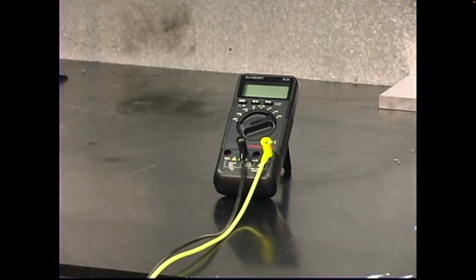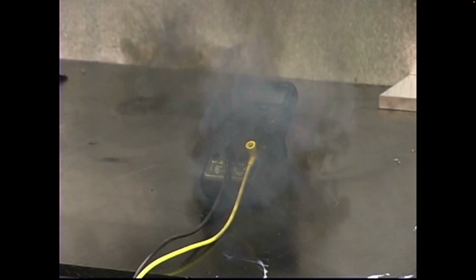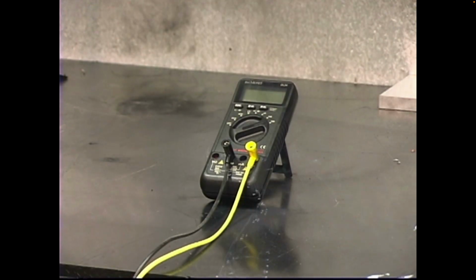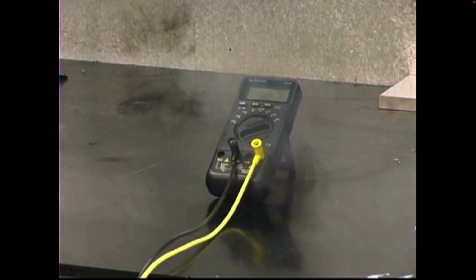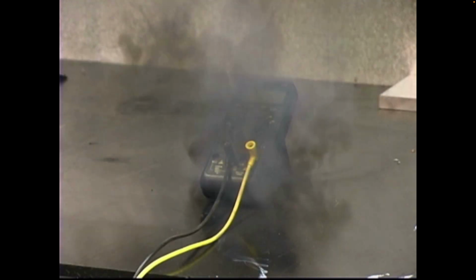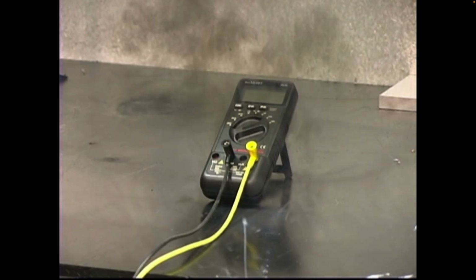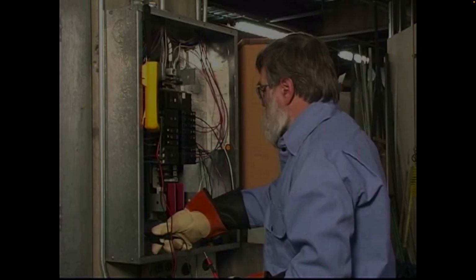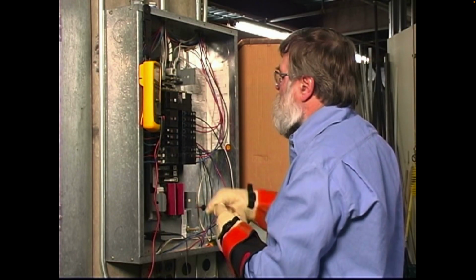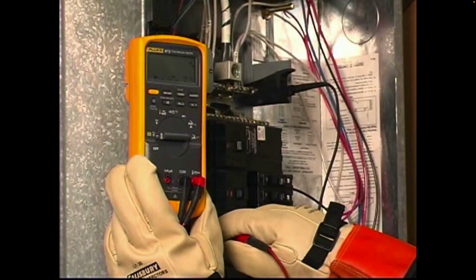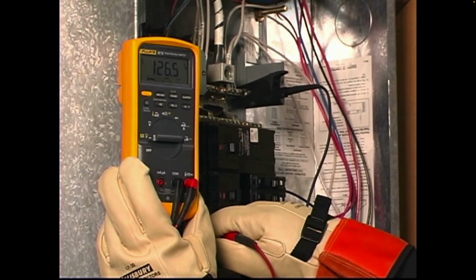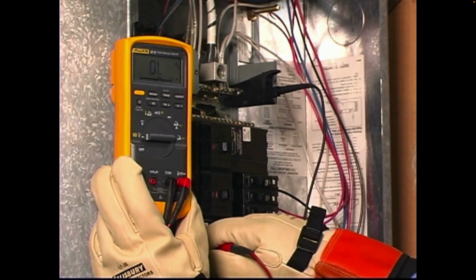Here's what it does if you measure voltage using the amp's input jacks. The fuse would not protect the meter or user. Just imagine if this meter was in your hand and used on a real Cat3 circuit. Even the most careful of us will make mistakes. That's why, if an inappropriate voltage is applied, your meter should offer a margin of protection.